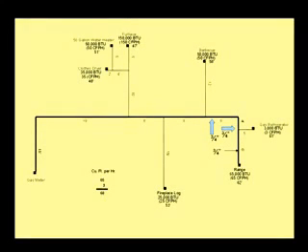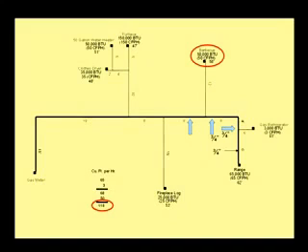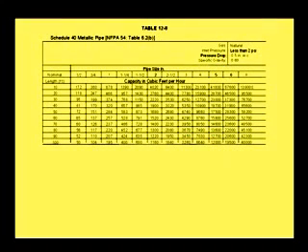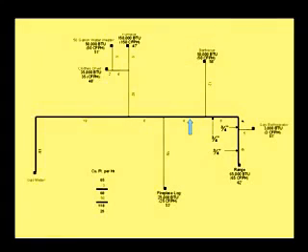The next section of pipe will be supplying the branch to the barbecue with a demand of 50 cubic feet per hour, plus the 68 cubic feet per hour from the previous appliances, for a total demand of 118 cubic feet per hour. Refer to table 12-8, 70-foot row — 118 fits under 126 — and see that a 3/4-inch pipe will accommodate the 118 cubic feet per hour demand for the 8-foot section.